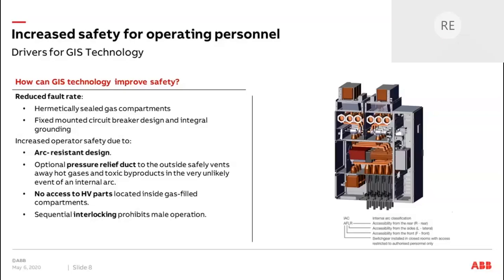In GIS technology, we use fixed mounted circuit breakers and integral grounding devices instead of withdrawable circuit breakers like in AIS. Which means that on the one hand, we prevent the operator from accessing any of the high voltage parts, and on the other hand, no mistakes can happen while racking in and racking out a breaker. In addition, most of the common designs on the market are arc resistant, which means they are internal arc type tested either according to the IEC or the ANSI standard. Some of the designs also offer optional pressure relief ducts that would vent away any hot gases and toxic byproducts in the very unlikely event of an internal arc.